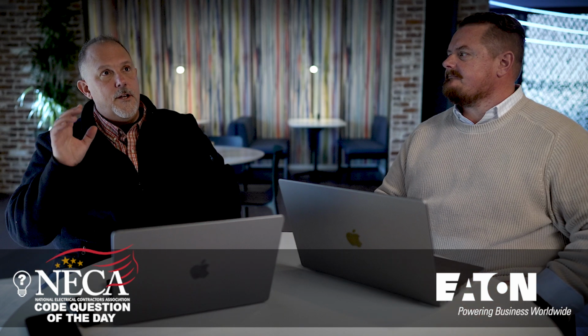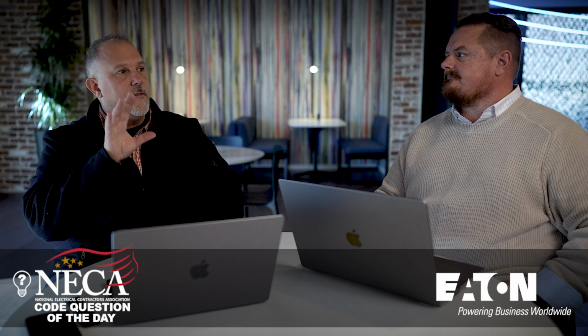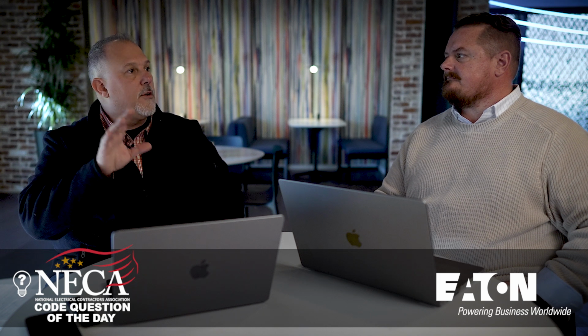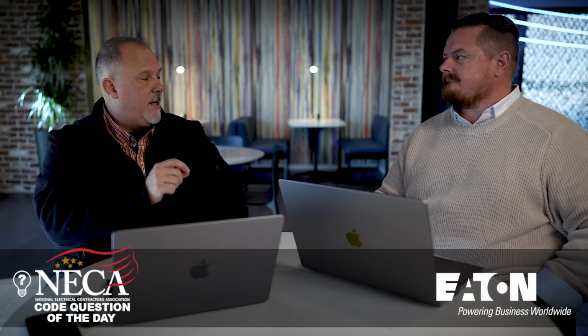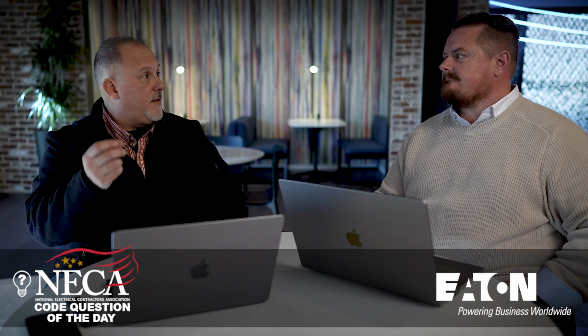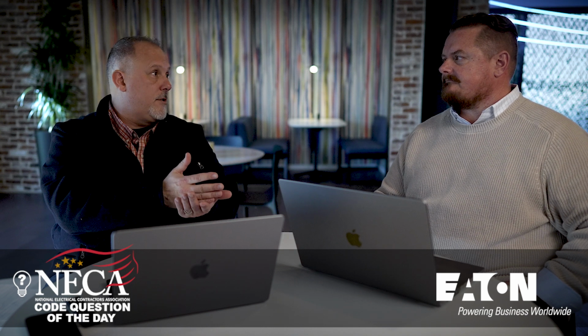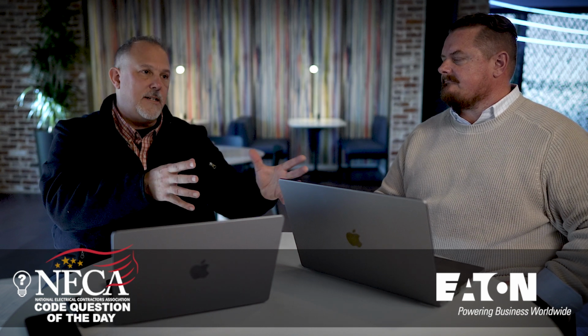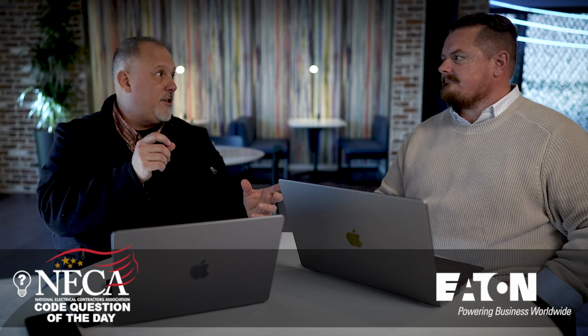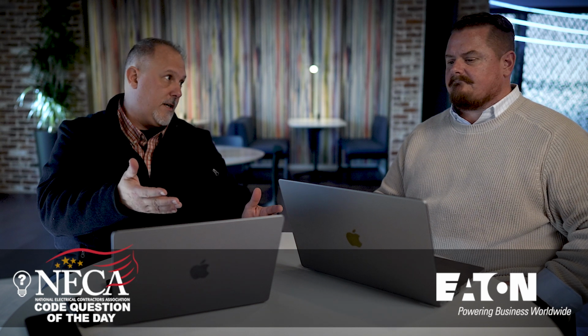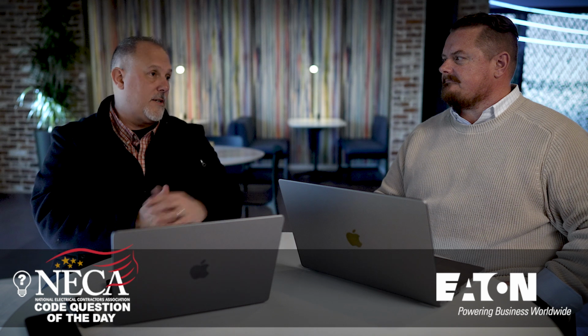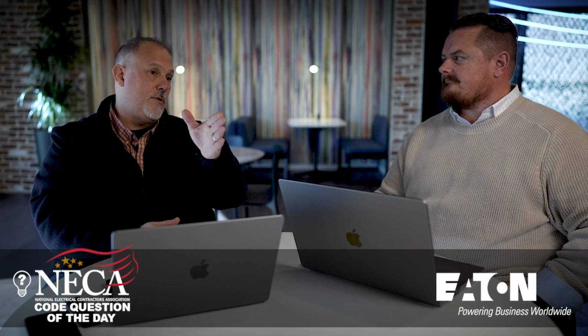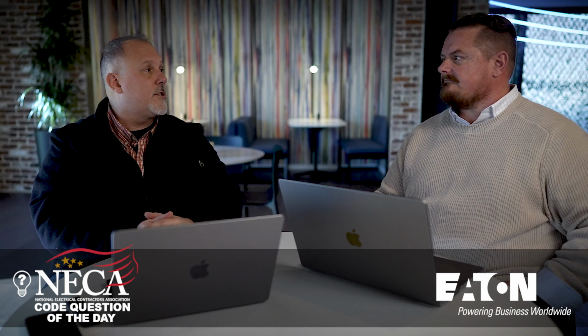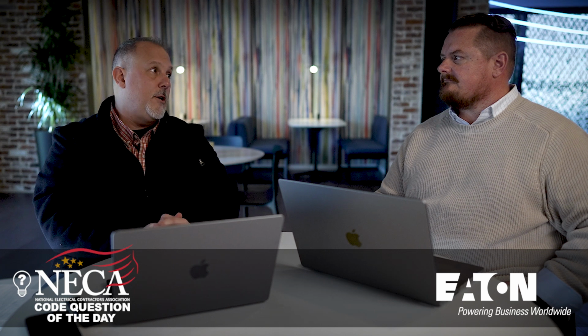So short circuit current rating is the ability of the product to withstand current passing through it, and interrupting rating is the ability of the overcurrent device to stop the flow of current. So SCCR doesn't change just because you have a high interrupting rating overcurrent device. I have people do this: they'll say, well, I have a fuse as the main, it's 200,000, so I've automatically got a 200,000 amp short circuit current rating. And you don't.